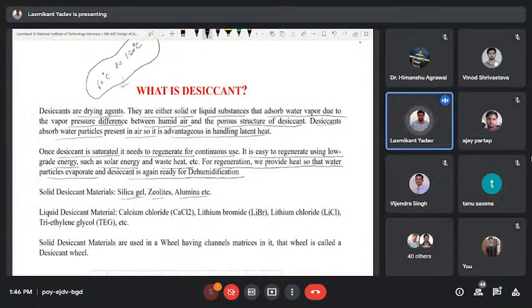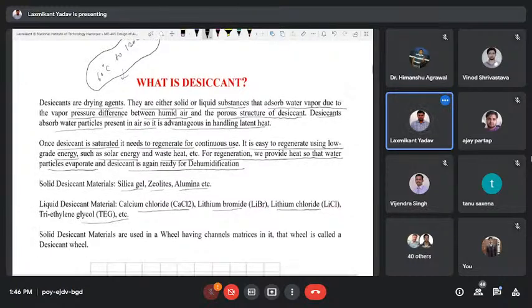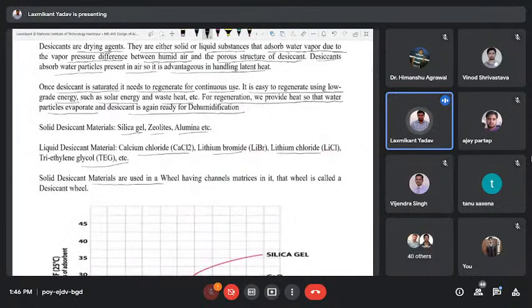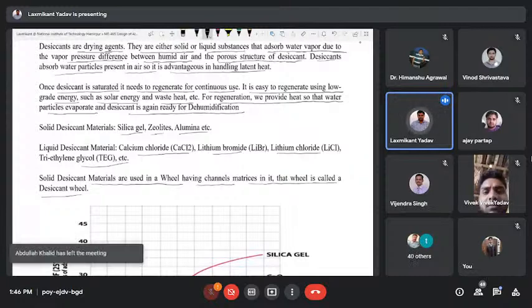And liquid desiccants are calcium chloride, lithium bromide, lithium chloride, and triethylene glycol. Okay. Solid desiccant materials are used in a wheel having channel matrices in it. That wheel is called a desiccant wheel. So the desiccant wheel is called a rotary dehumidifier for the production of dry air. So basically that wheel is the rotary wheel.